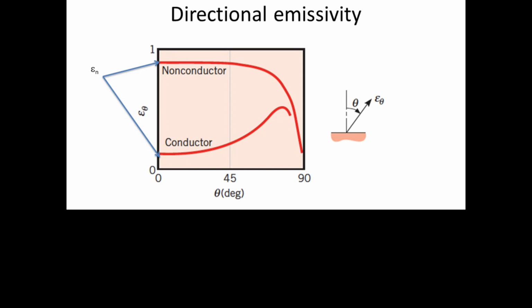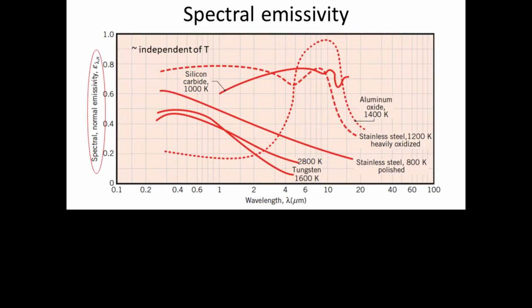So these things make it very difficult. To give you an idea, when a guy comes to do drywall inspections and comes with a thermal camera, if you say, okay, give me a temperature, they couldn't easily do it because they need to assign an emissivity to give you a temperature. And that emissivity depends on the angle, depends on wavelength, depends on many things. Very tricky. So when you're getting into these issues of thermal imaging, you better know what you're talking about, because it's always pretty, but that doesn't mean you know what you're doing.